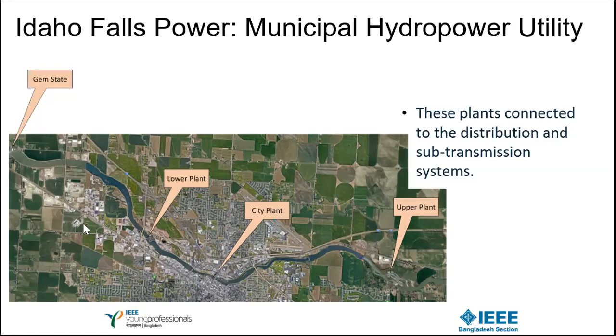As you step up the load demand to the hydropower, there is a transient event. It will see a sudden drop of the frequency, but the rotating mass of the hydropower will try to catch up pretty fast so that the frequency does not drop too far below the protection setting. Otherwise, it will trip the hydropower off the grid again, and then there is no meaning of the black start. That's the ideal case. But what actually happens is that as the hydropower plant reaches its capacity, say it's currently supporting 6 megawatt, and then you step up to 7 megawatt, that additional 1 megawatt may cause a frequency instability so severe that it can trip the generation off the distribution grid again.